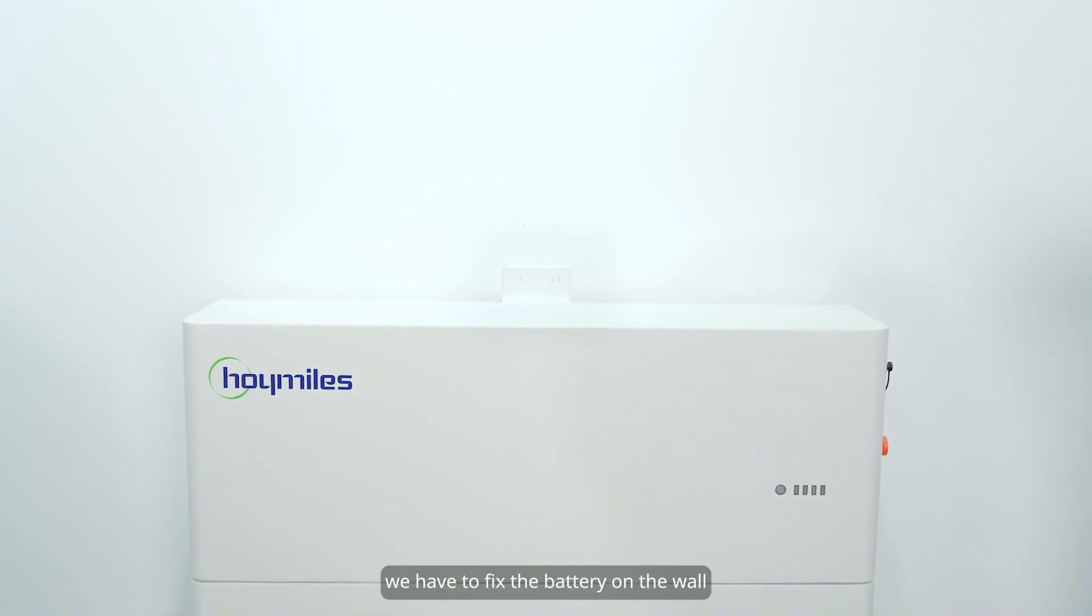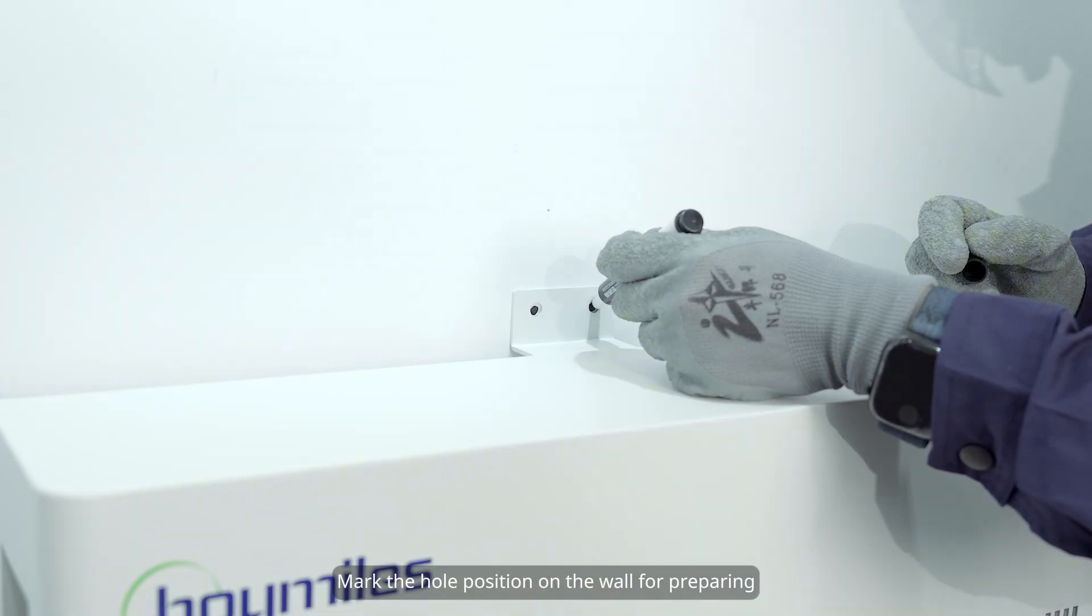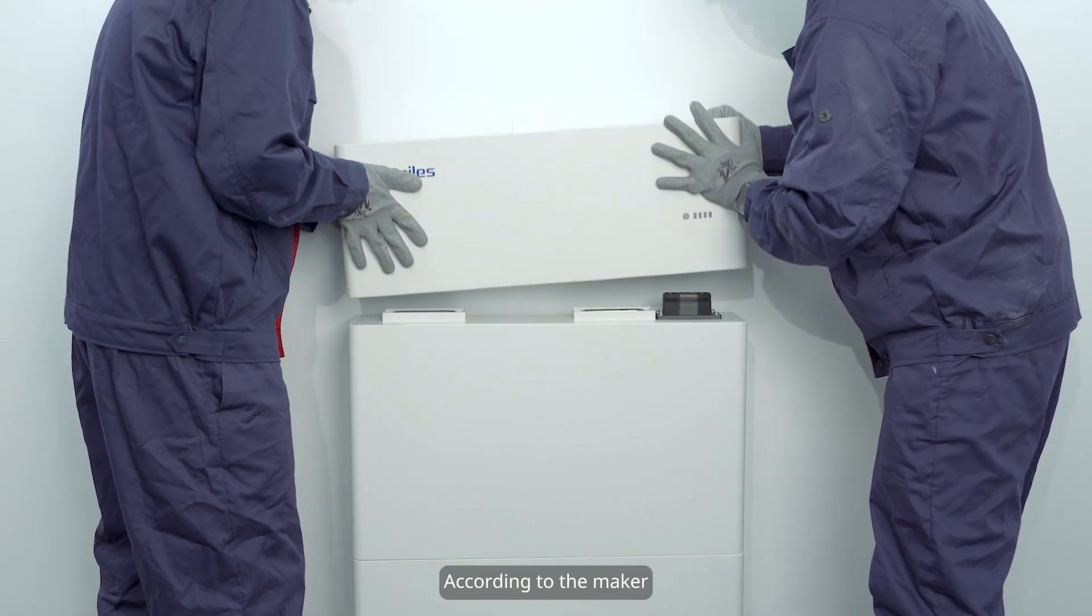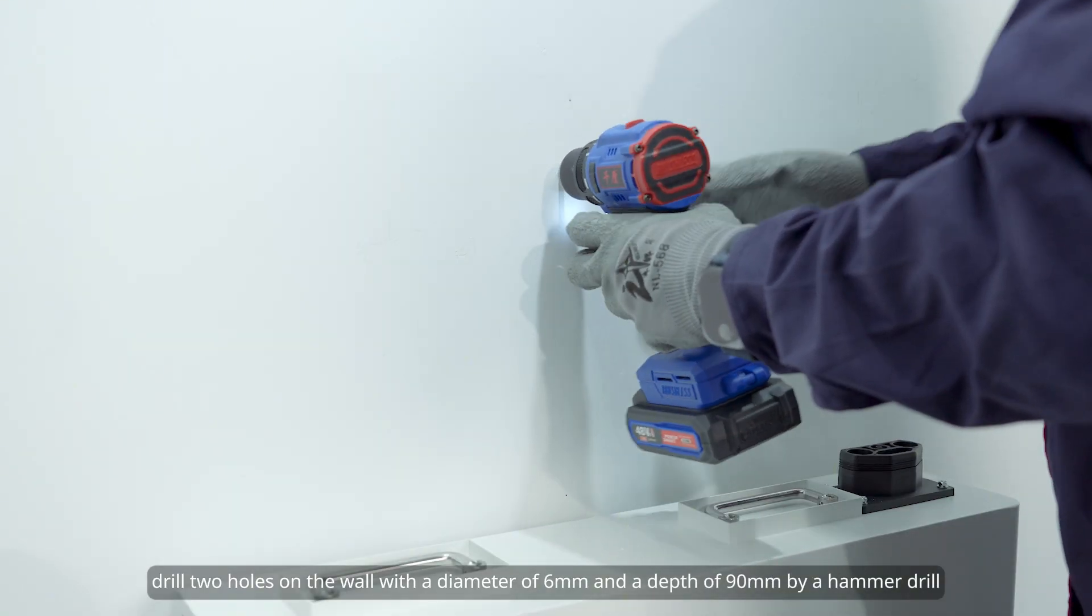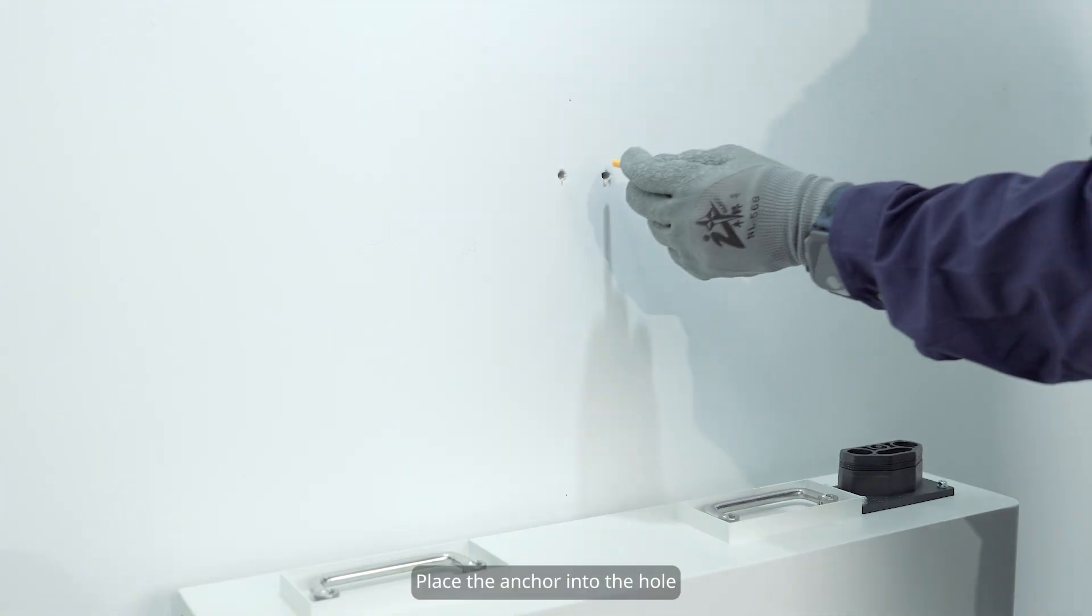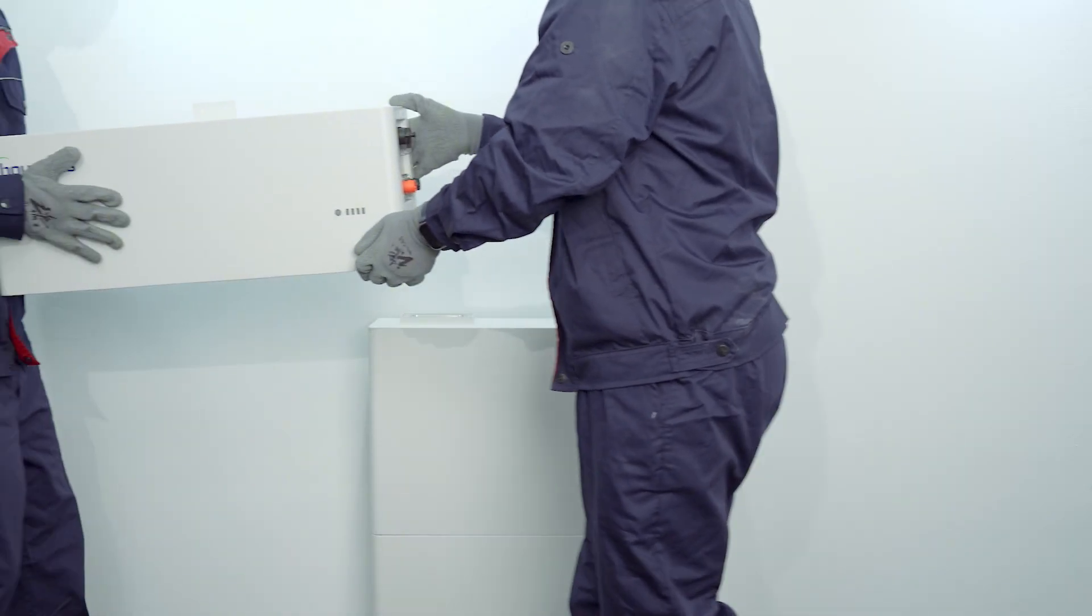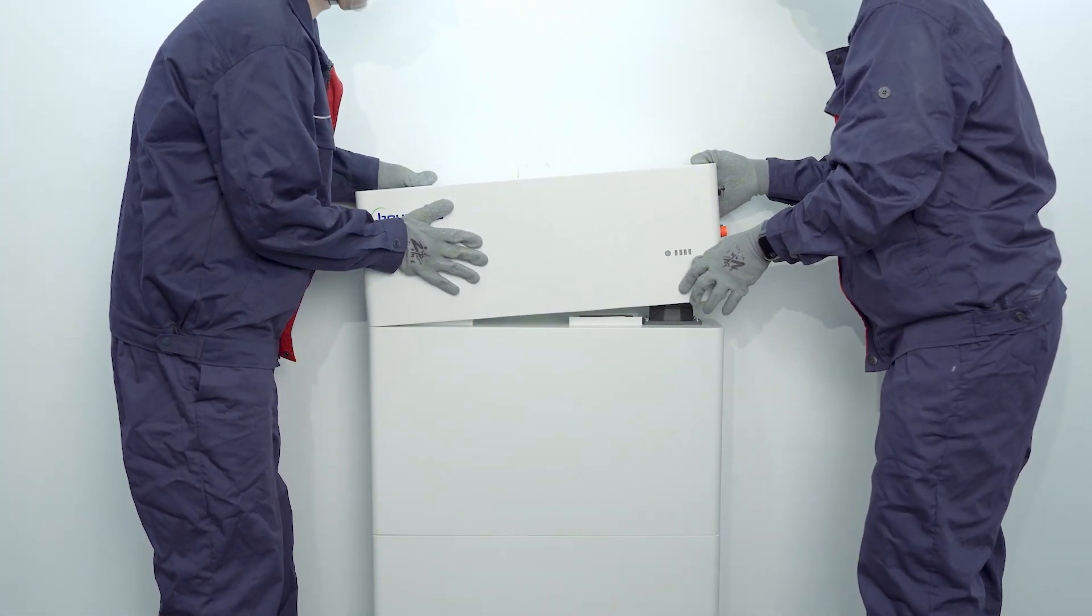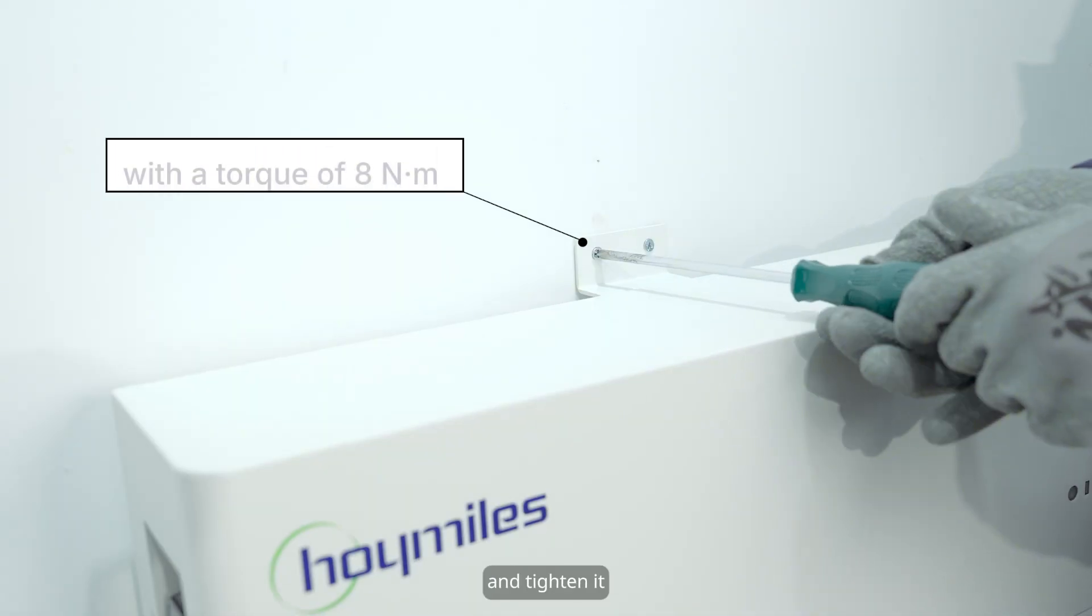The next step, we have to fix the battery on the wall. Mark the hole position on the wall for preparing. According to the marker, drill two holes on the wall with a diameter of 6 millimeters and a depth of 90 millimeters by a hammer drill. Place the anchor into the hole. Insert the M6 screw into the anchor and tighten it.